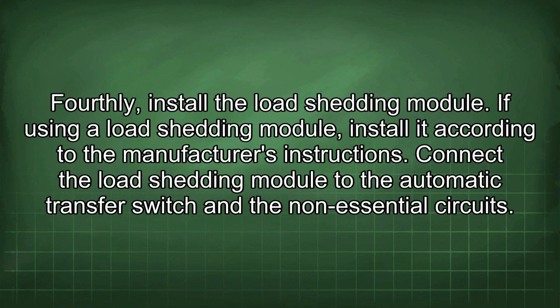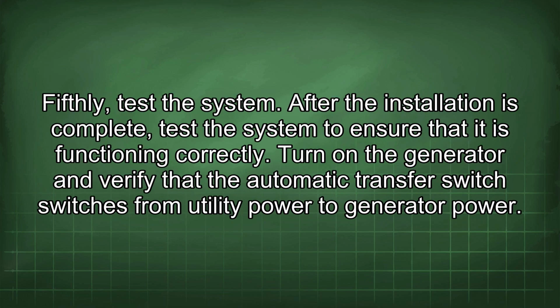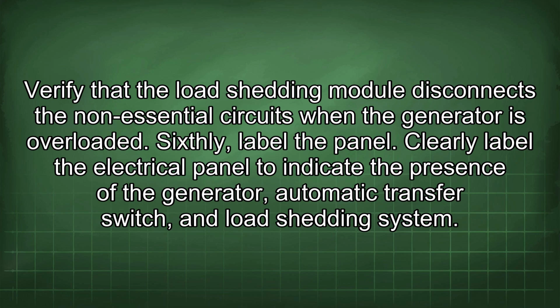Fourthly, install the load shedding module. If using a load shedding module, install it according to the manufacturer's instructions. Connect the load shedding module to the automatic transfer switch and the non-essential circuits. Fifthly, test the system. After the installation is complete, test the system to ensure that it is functioning correctly. Turn on the generator and verify that the automatic transfer switch switches from utility power to generator power. Verify that the load shedding module disconnects the non-essential circuits when the generator is overloaded.